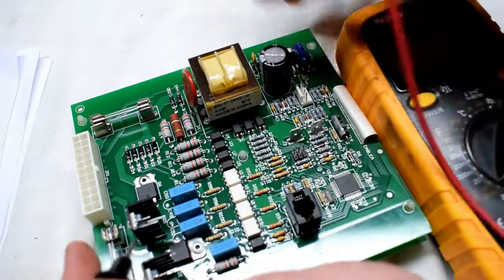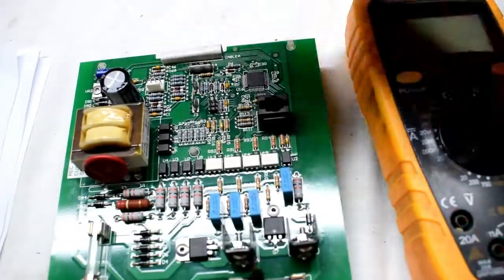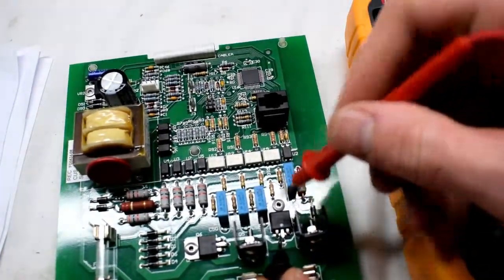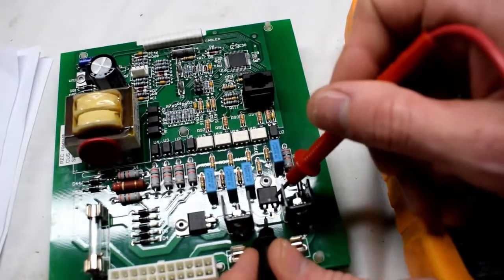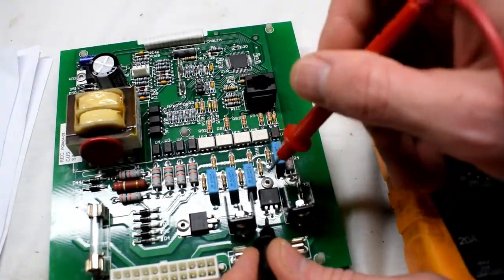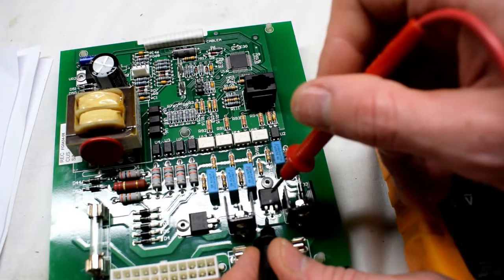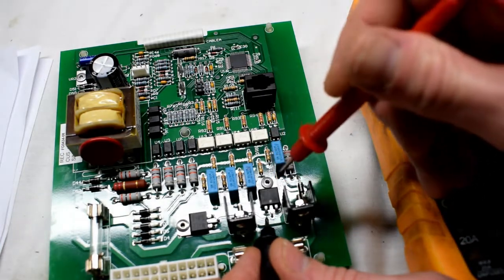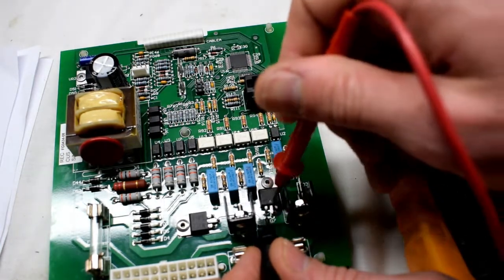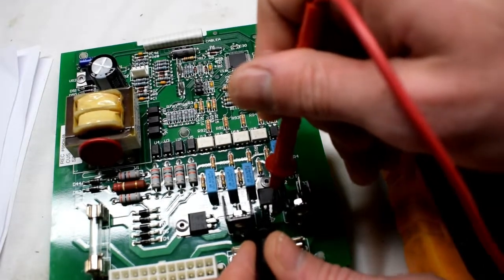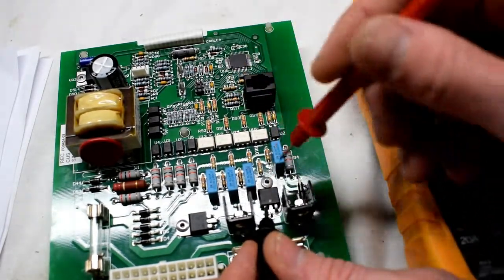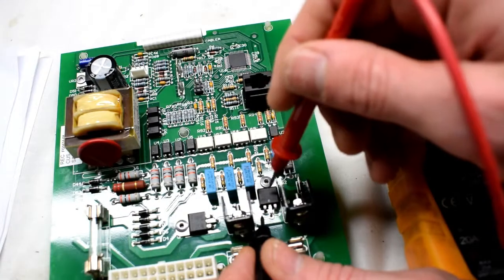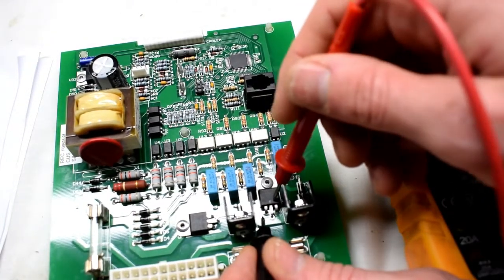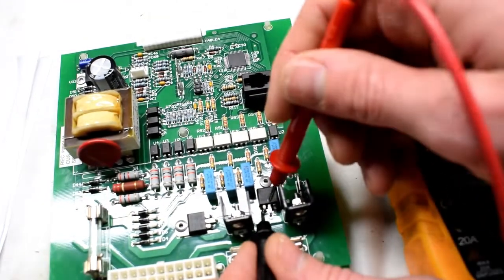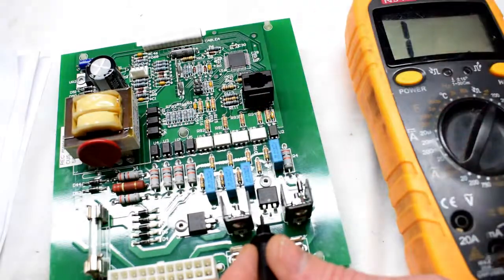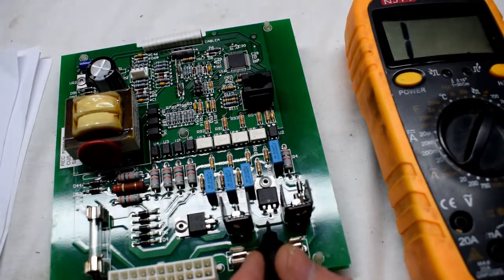So right away I know that this chip probably has something wrong, or if that's not the problem, it could be another component that is connected in parallel with that, in between those two legs. But that should not be a short right there. So what I'm going to be doing is I'm going to desolder this chip and test it. And if I desolder and test that and it's still short, I know that this is the bad chip and I need to replace it.